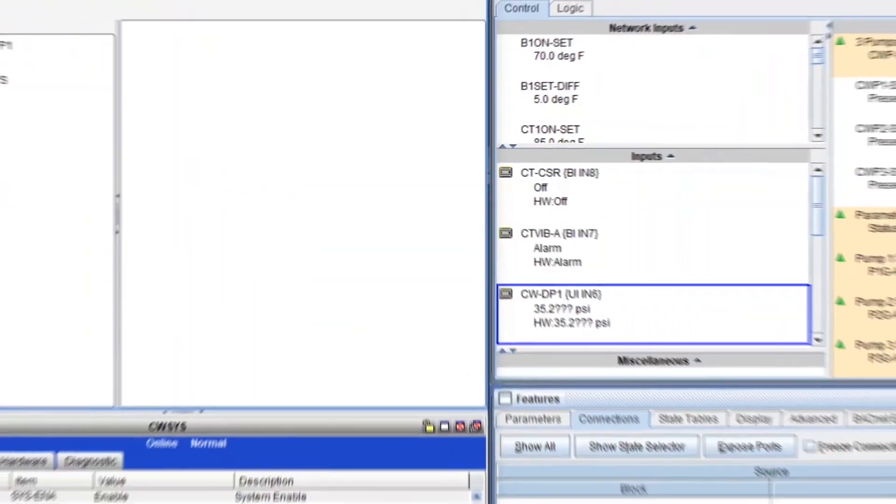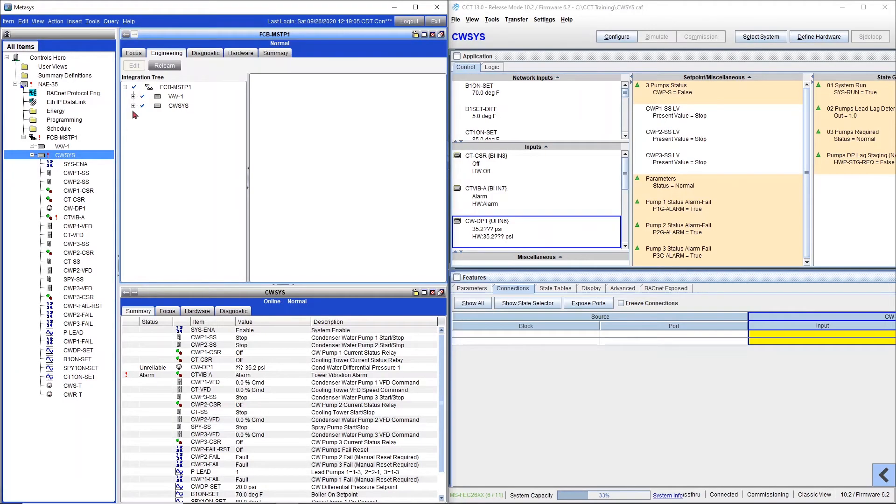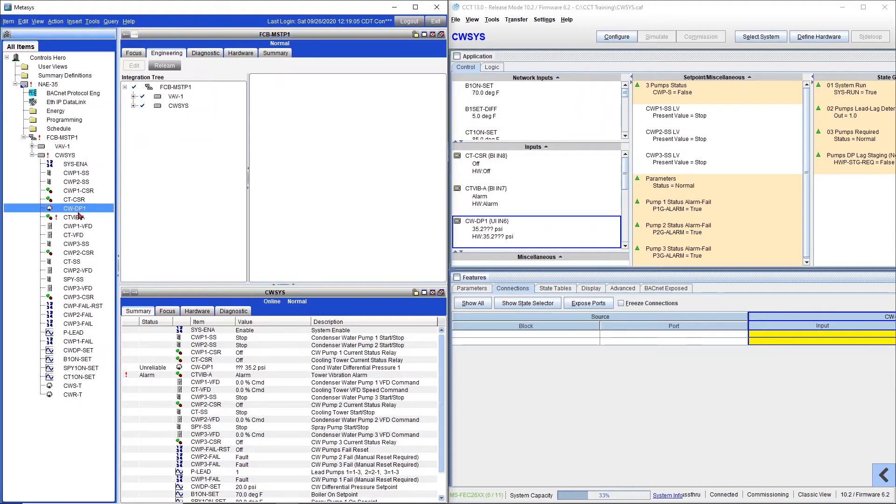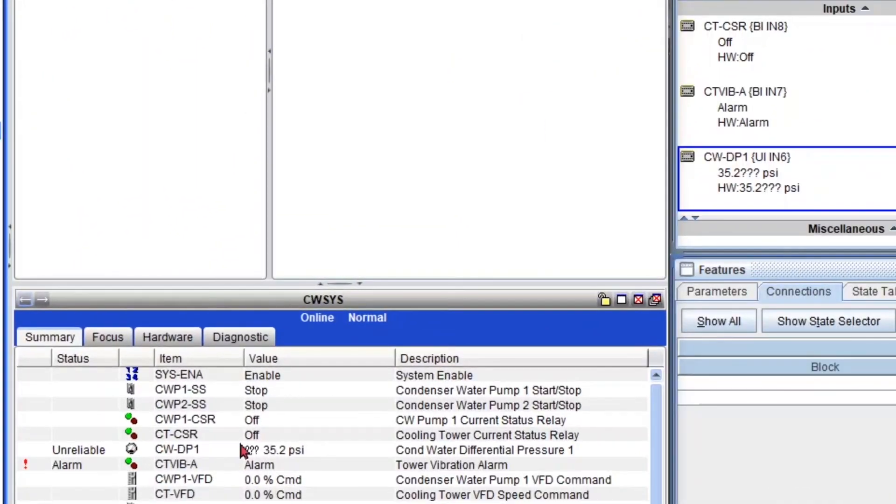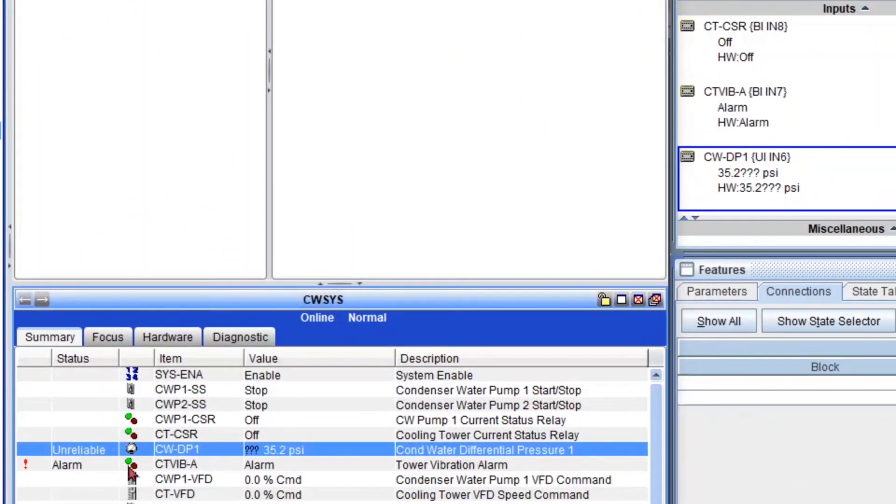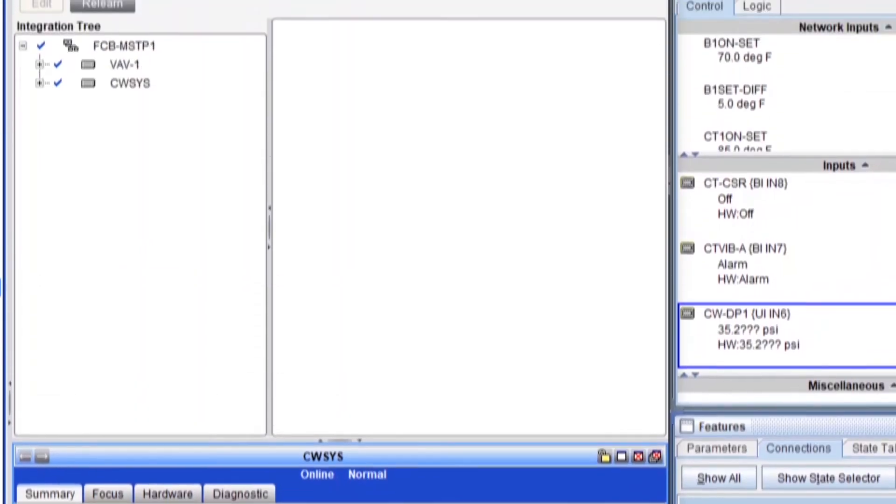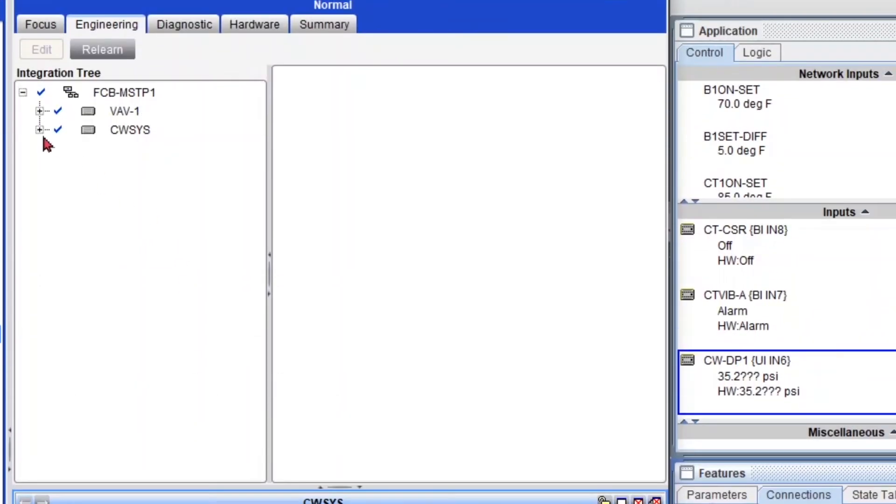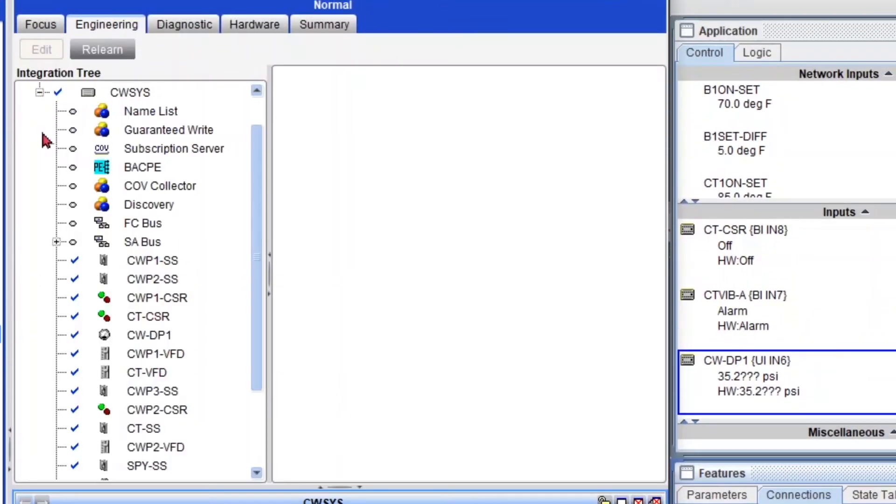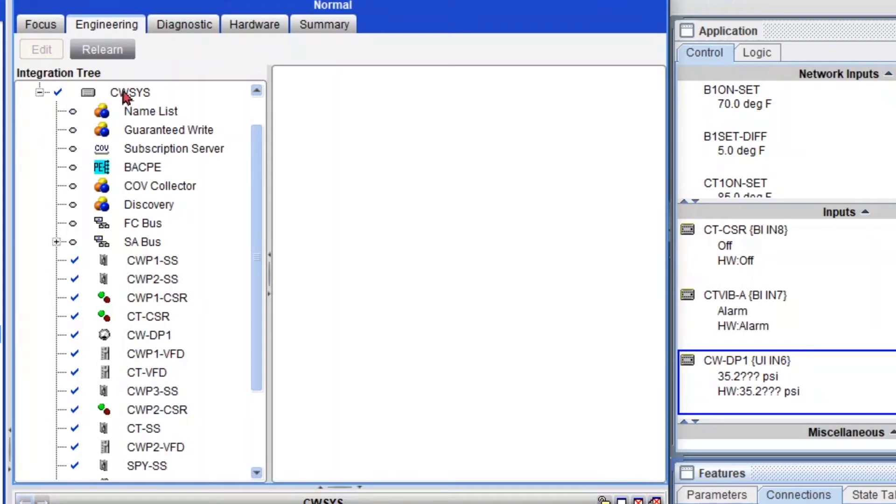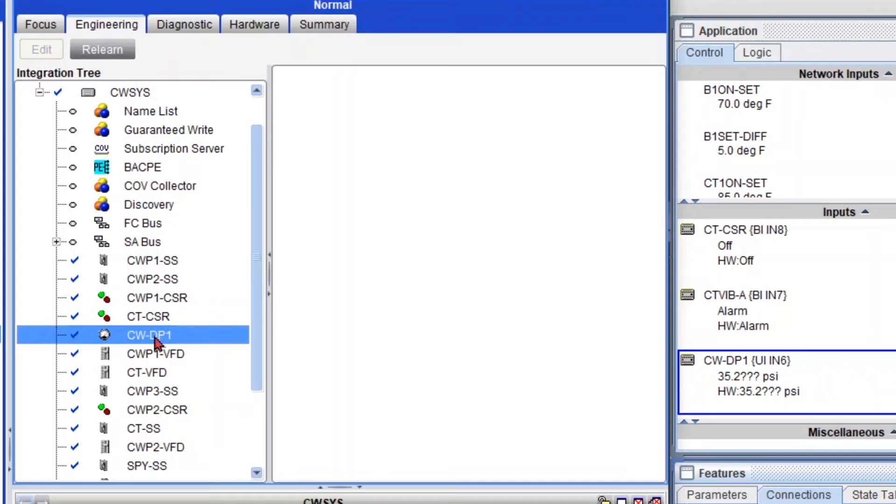Okay, now let's change the parameters of an analog input. A differential pressure sensor. So we have our condenser water system here. So here's our sensor. And it is unreliable and it has a couple of issues. So I'm going to show you. So let's expand my condenser water system under my engineering tab. And let's look for that sensor, which is right here.